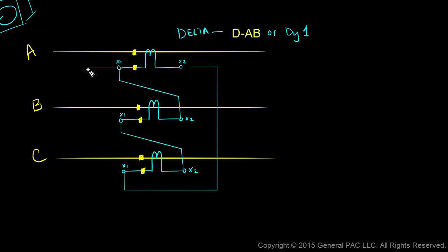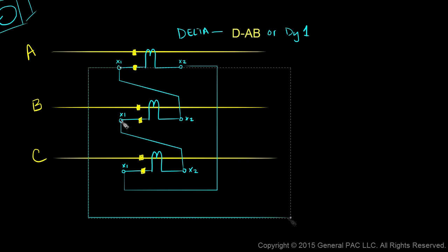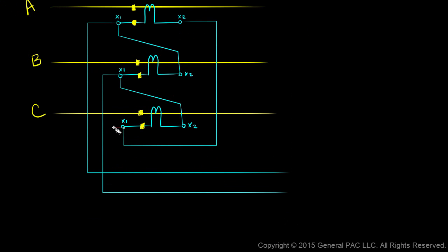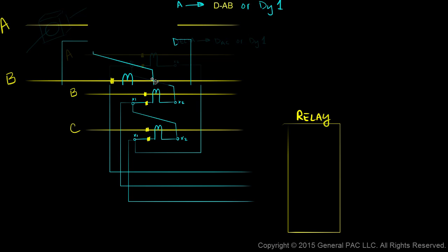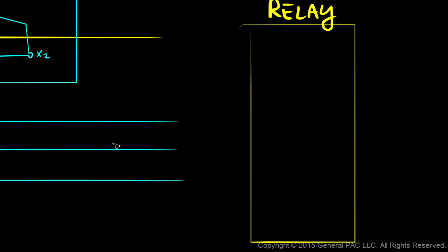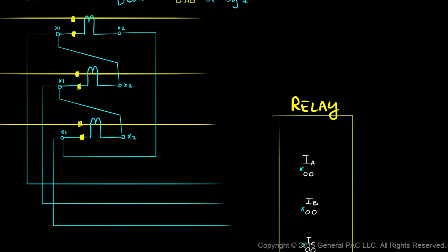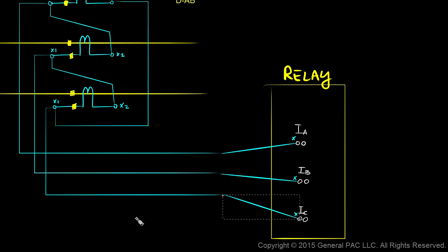Now we connect the X1 bushing of our CTs to our relay. Our relay has terminal inputs for Phase A, Phase B, and Phase C. One of these input terminals is marked as the polarity side. The polarity side of our CT conductor — the X1 bushing — is connected to the polarity input terminal of the relay for Phase A, Phase B, and Phase C.